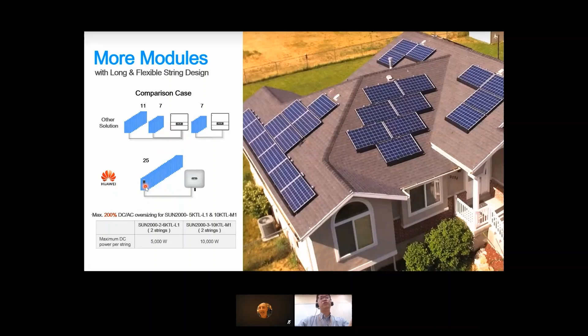For the single-phase inverter 2 to 6 KTL platform, each string can connect 5 kilowatts. So with 2 strings, it can connect 10 kilowatts of PV modules. If we are using a 5 kilowatt inverter, then the DC-AC ratio will be over 200%. Similarly, for the 3 to 10 KTL inverter, each string can connect 10 kilowatts, so 2 strings give 20 kilowatts, also a very high DC-AC ratio. And if you are using 400 watt modules, the string will be longer compared to conventional string inverters. This can also help reduce cable and BOS cost.